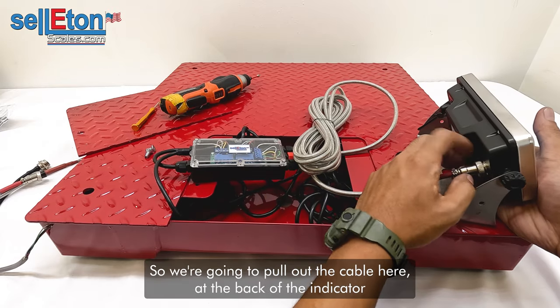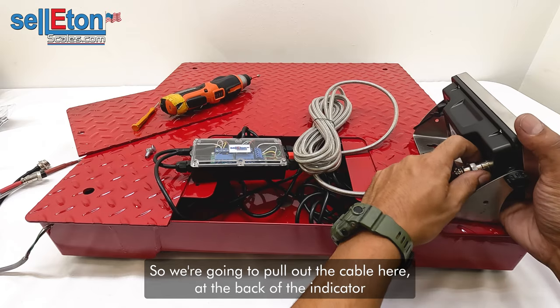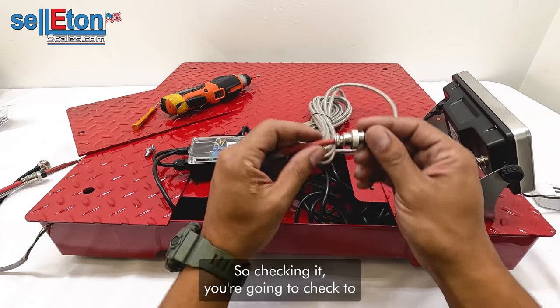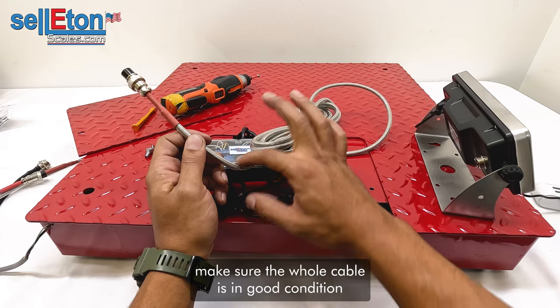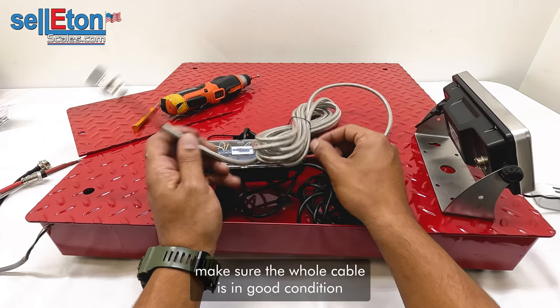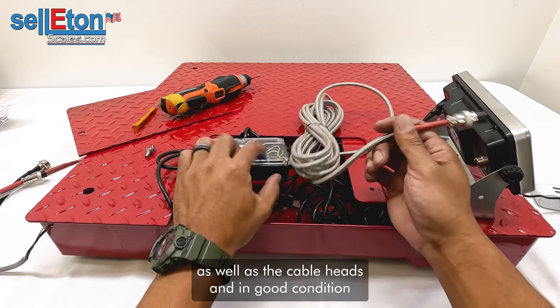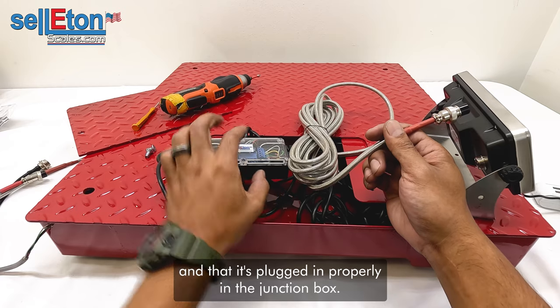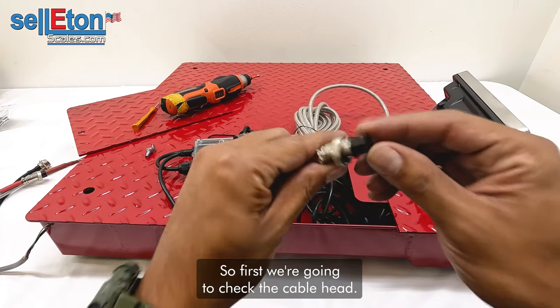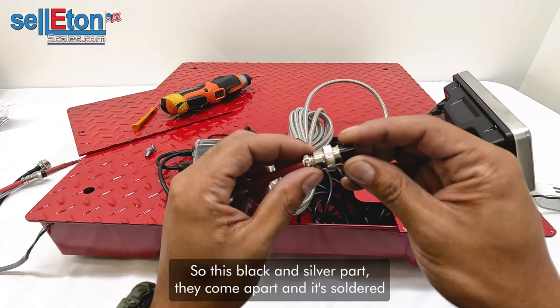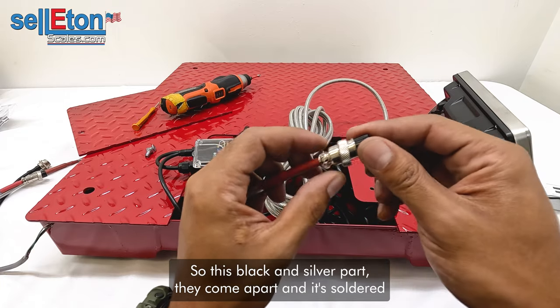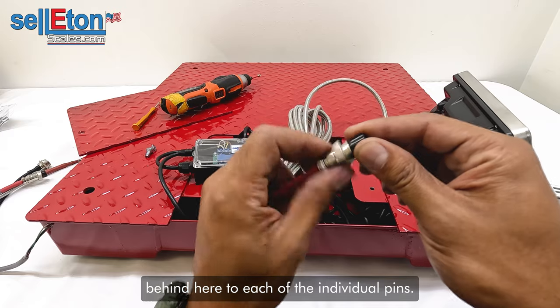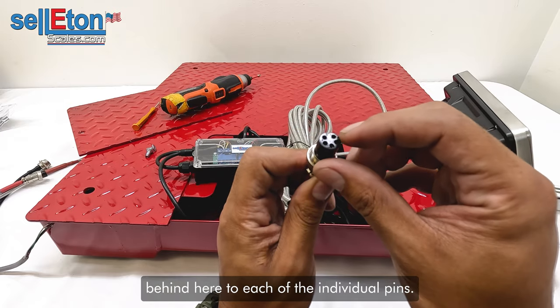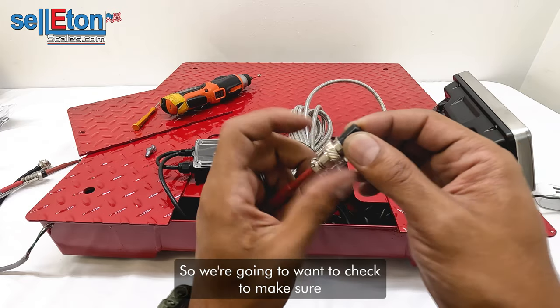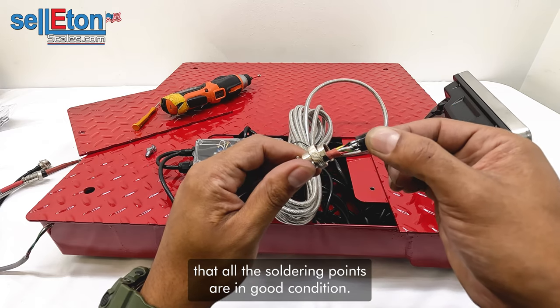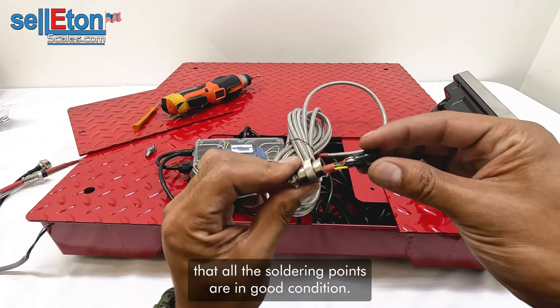So we're going to pull the cable out of the back of the indicator and check it. You're going to check to make sure the whole cable is in good condition, as well as the cable head, and that it's plugged in properly in the junction box. First we're going to check the cable head. This black and silver part comes apart, and it's soldered behind here to each of the individual pins. We want to check to make sure that all the soldering points are in good condition.